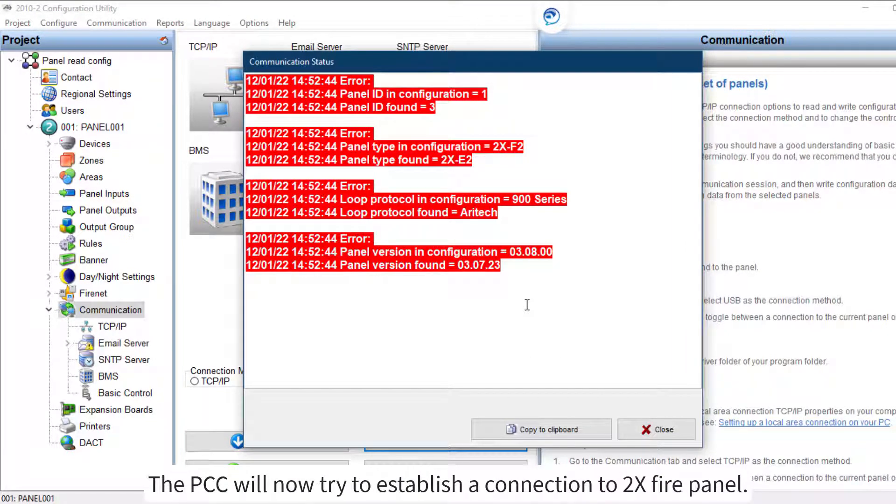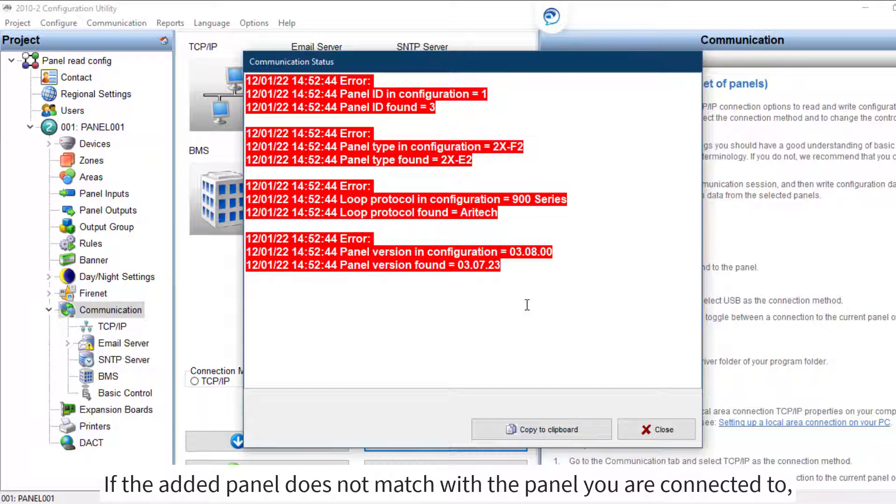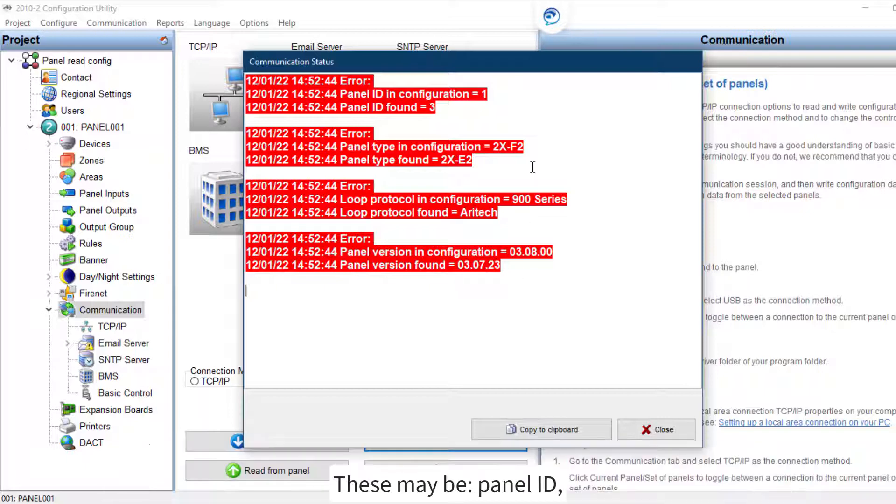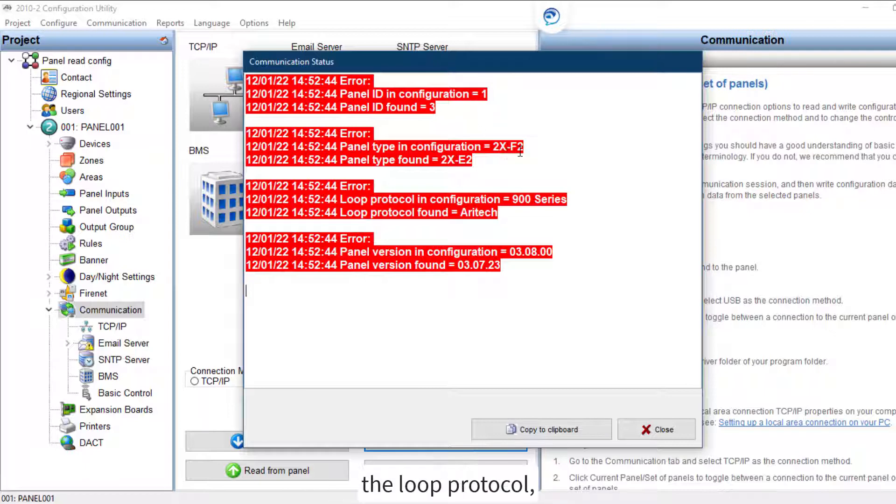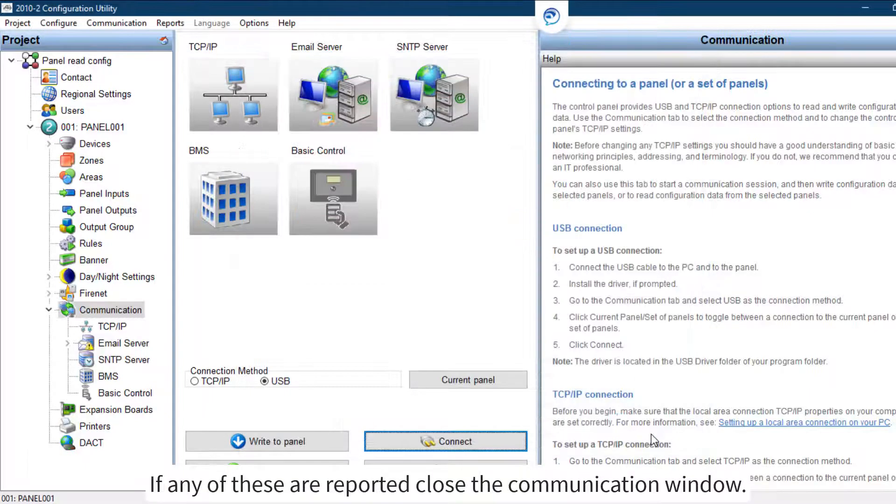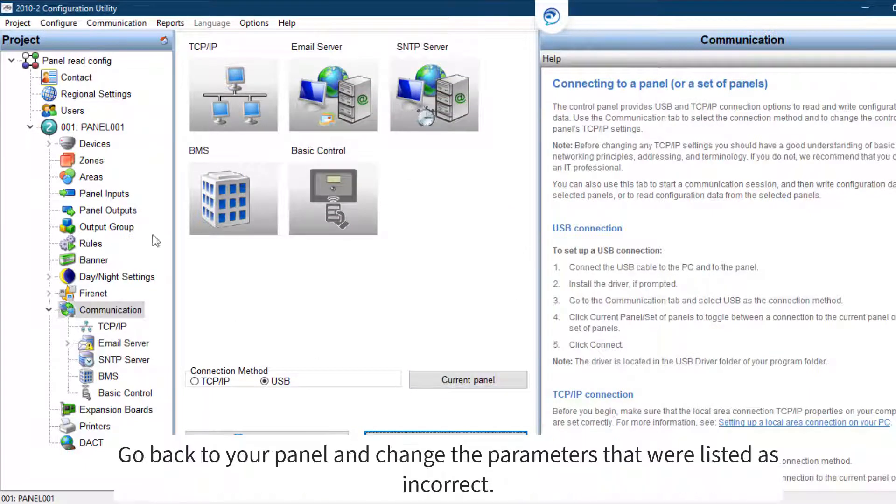If the added panel does not match with the panel you are connected to, the PCC will display faults and indicate the wrong settings that need to be corrected. These may be panel ID, the panel type, the loop protocol, or panel version. If any of these are reported, close the communication window and go back to your panel.